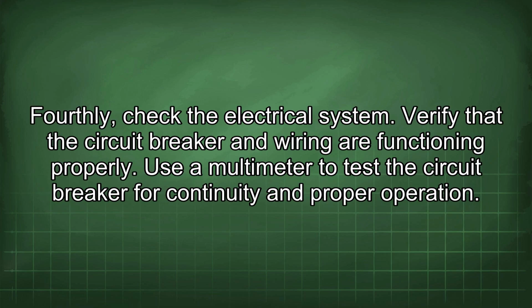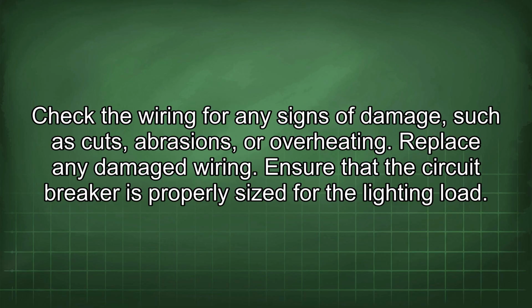Fourthly, check the electrical system. Verify that the circuit breaker and wiring are functioning properly. Use a multimeter to test the circuit breaker for continuity and proper operation. Check the wiring for any signs of damage such as cuts, abrasions, or overheating. Replace any damaged wiring. Ensure that the circuit breaker is properly sized for the lighting load.